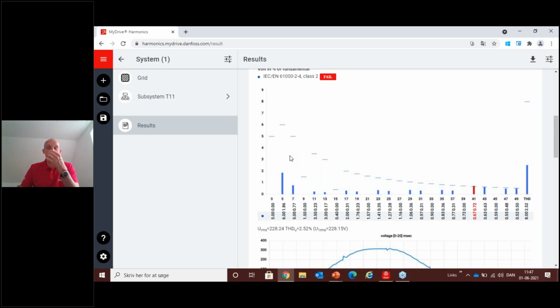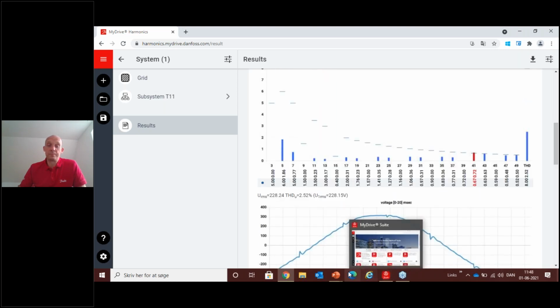That's also the reason why I'm trying to persuade you to be extremely cautious in what you're selecting. You need to make sure you know what you're doing, and you should only add mitigation equipment when it's really needed. In this specific example, it's a pretty dumb idea to add mitigation equipment, because you end up destroying your picture. If you have a resonance point on your supply grid around the 41st harmonic, times 50, so what is that, 2 kilohertz, then it will be excited by the harmonic here, and you will have an installation that might start giving you issues.